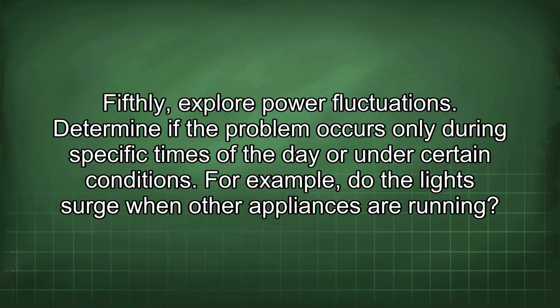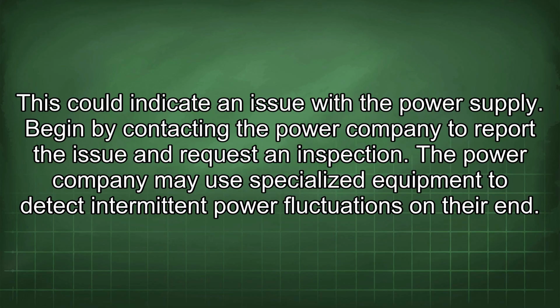Fifthly, explore power fluctuations. Determine if the problem occurs only during specific times of the day or under certain conditions. For example, do the lights surge when other appliances are running? This could indicate an issue with the power supply. Begin by contacting the power company to report the issue and request an inspection. The power company may use specialized equipment to detect intermittent power fluctuations on their end.